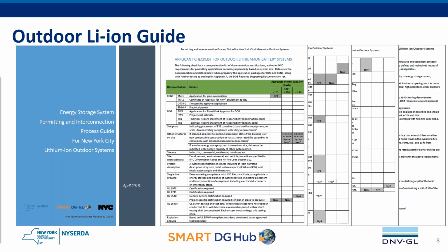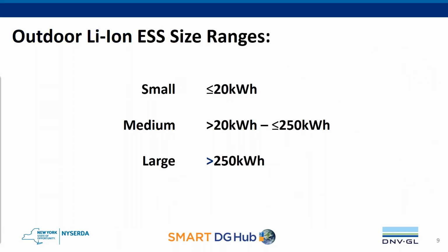So I'm going to dive a little deeper into what these guidelines pertain to. First, just a baseline: we termed small systems to be systems under 20 kWh. Medium systems were over 20 kWh but under 250, and large were exceeding 250 kWh. The idea here is to make sure that the things that might be appropriate to consider for a very, very large energy storage system may not be as applicable to small residential systems. This also follows size ranges that are included in up-and-coming standards and other standards that are coming out.